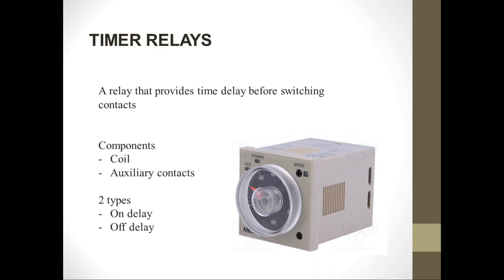Once the on-delay timer is de-energized — that is, the supply is cut off — the auxiliary contacts immediately go back to their initial position. For the off-delay type timer, when the coil is energized with the rated voltage, the auxiliary contacts automatically switch or change position.